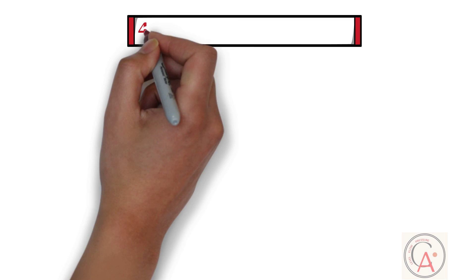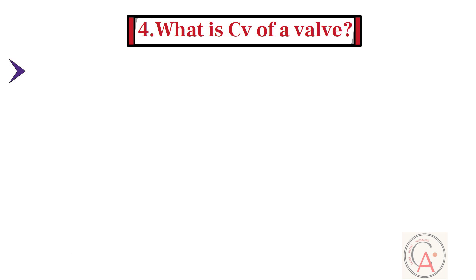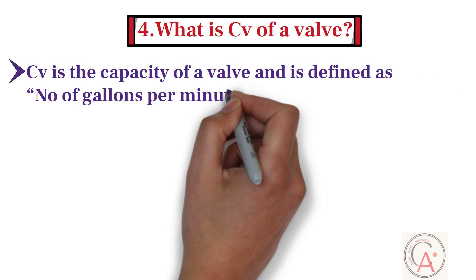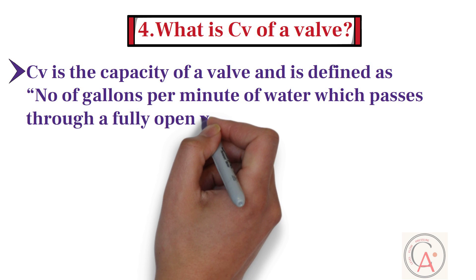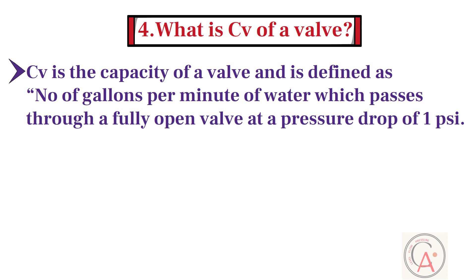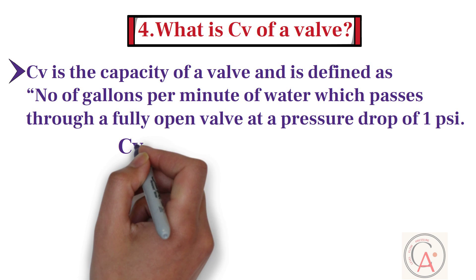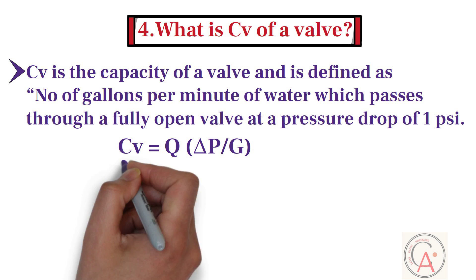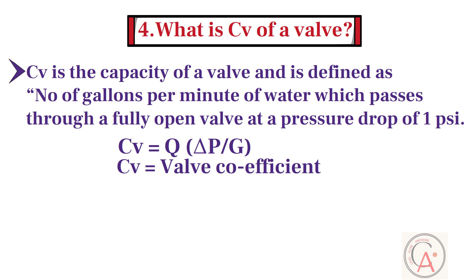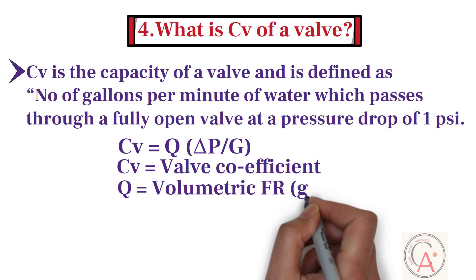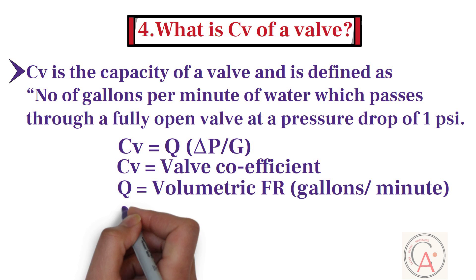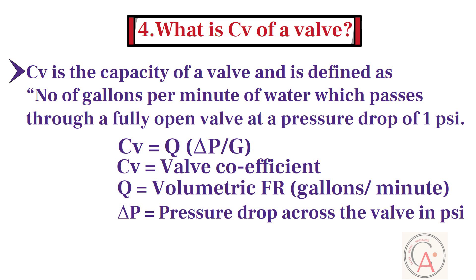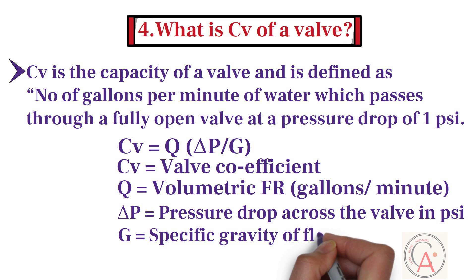Fourth question: what is the CV of a valve? CV is the capacity of a valve, defined as the number of gallons per minute of water which passes through a fully open valve at a pressure drop of one pound per square inch. In the CV equation: CV is the valve coefficient, Q is the volumetric flow rate, ΔP is the pressure drop across the valve in psi, and G is the specific gravity of the flowing fluid.